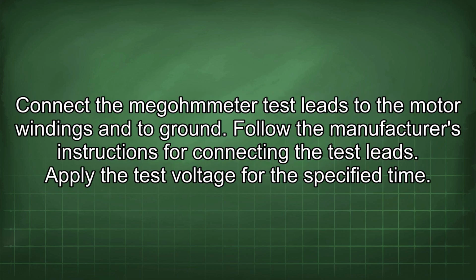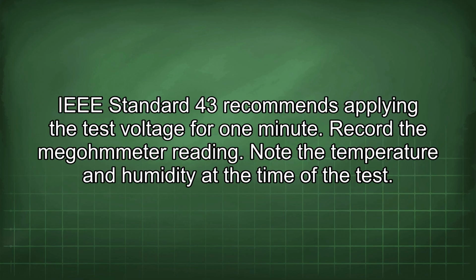Connect the megohmmeter test leads to the motor windings and to ground. Follow the manufacturer's instructions for connecting the test leads. Apply the test voltage for the specified time. IEEE Standard 43 recommends applying the test voltage for 1 minute. Record the megohmmeter reading. Note the temperature and humidity at the time of the test.